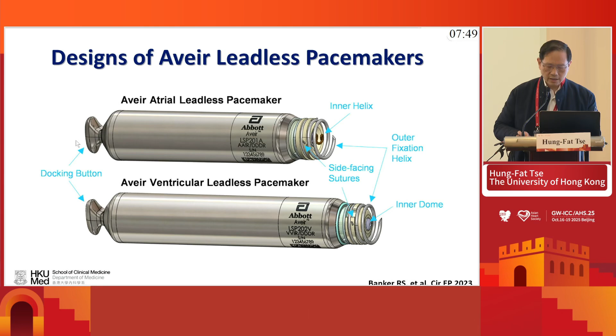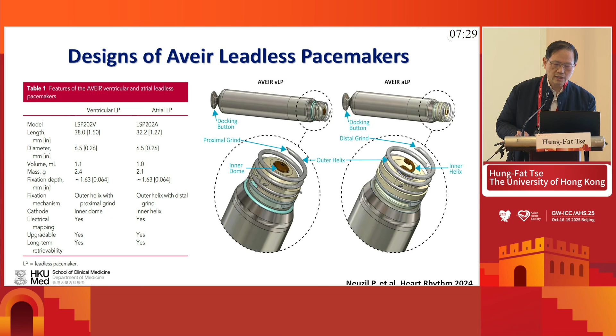And again, if you look more closely, you see that the size is smaller in the atrial device compared to the ventricular device. That's why the longevity is shorter. But again, the device also differs, with shorter longevity because of the lower impedance, because of the additional helix inside that actually reduces the impedance for the device.